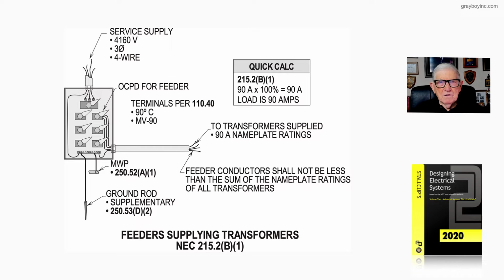Now let's take a look at this figure 17-16 from Stallcup's Electrical Design Book, Volume 2, and we're dealing with calculating the load for high voltage feeders in accordance with 215.2(B)(1). And you can see that we take 90 amps at 100%, and the load would be 90 amps. And we're dealing with terminals per 110.40, which are 90 degrees C, medium voltage, 90.